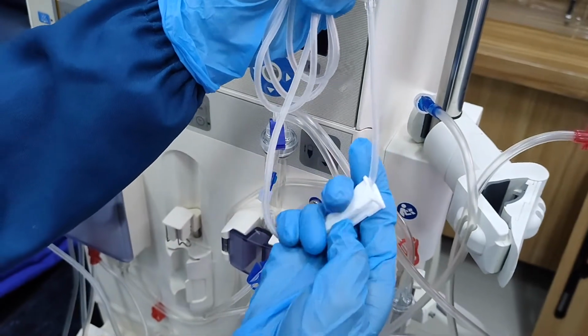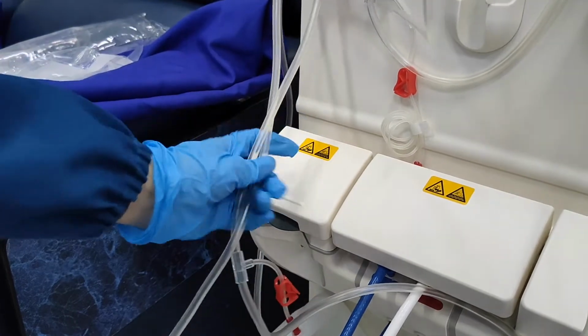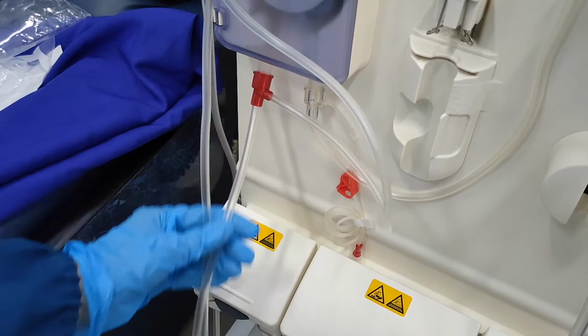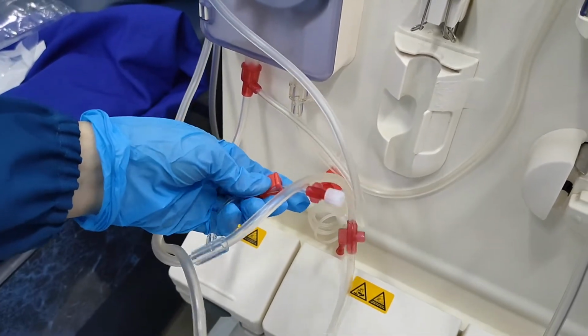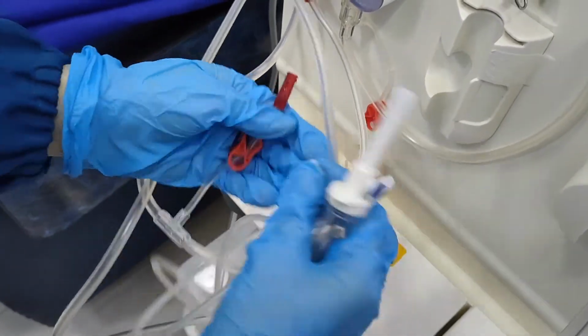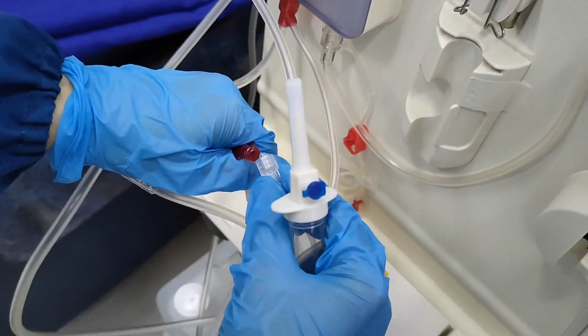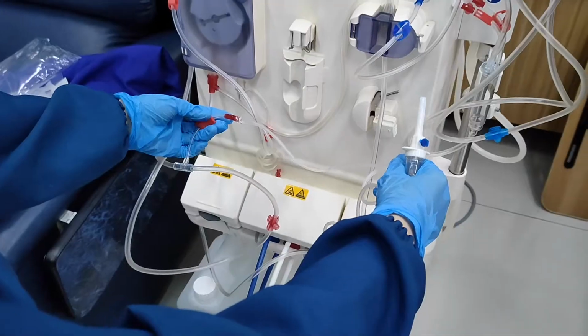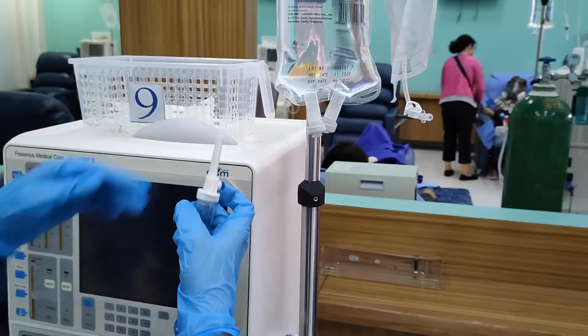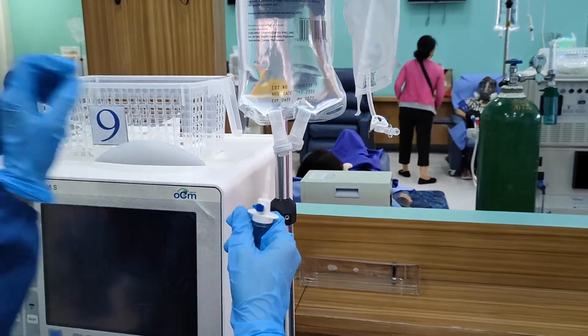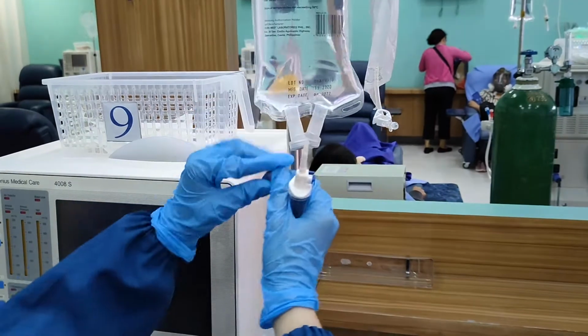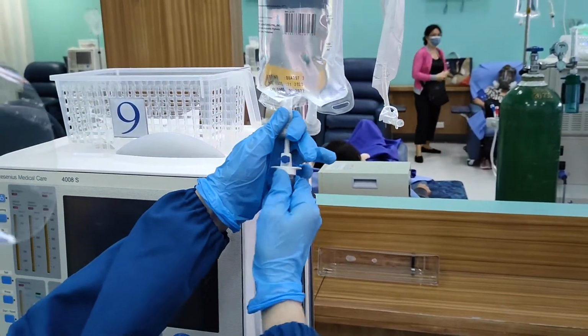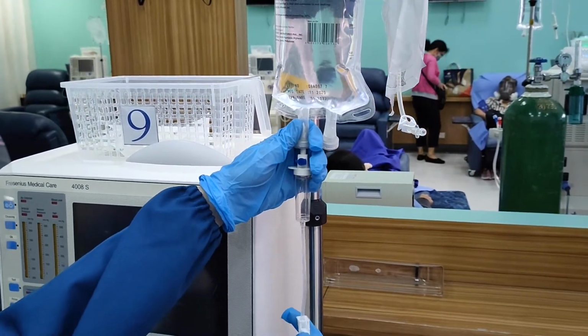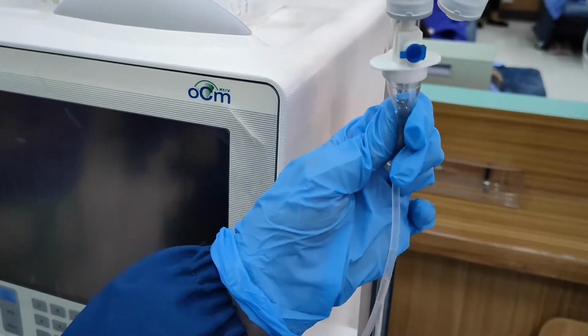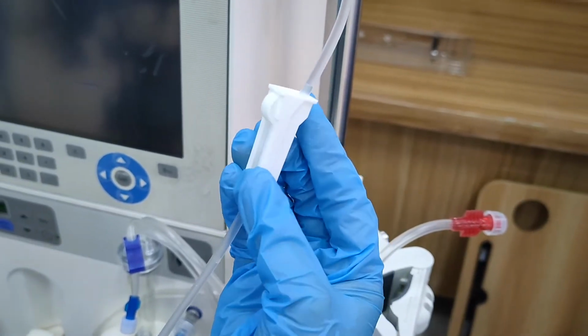Then get the IV set, and make sure to close the roller clamp. Attach the port of the IV set to the arterial NSS line. Open the cap and spike the NSS. Fill the chamber about 3/4. Then open the roller clamp.